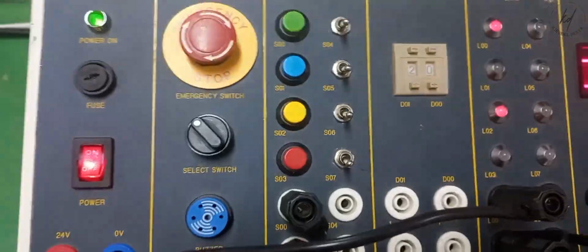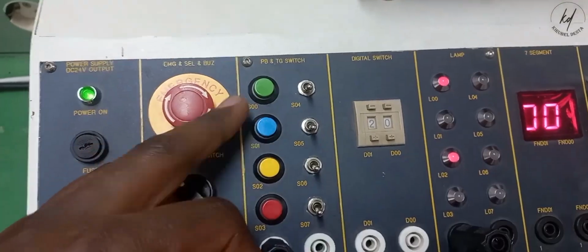In a star delta starter, initially, the motor is started in star configuration. The voltage across each phase is reduced by a factor of root 3. After a period of time the motor reaches 75 to 80% of full load speed, then the motor runs in delta configuration. A star delta starter is the most commonly used method for the starting of a 3-phase induction motor.